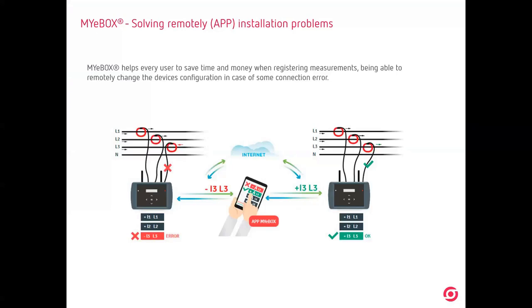A typical problem is this one that you see: if we are not connecting the current clamp in the correct way, we will not measure the current correctly. It will be seen as a negative in this example. If we have 10 plus 10 plus 10, it should be 30. If we have 10 plus 10 minus 10, it will be 10. Okay, so we are not measuring correctly. If the line is balanced, you see 10 plus 10 plus 10, and we know that we have to have 30, but this is unbalanced. You will never know the total energy, the total current.